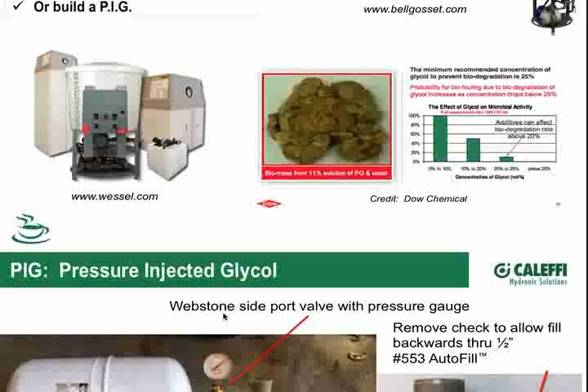This is a little system that another colleague gave me the idea for, and this is one I made. If you've got to boost up a system or fill a solar system that holds a little bit of fluid, you can pump glycol into a tank like this, put a pressure reducing valve on it, and just take it out to the job so you don't have to carry a big pump on a cart. Our fill valves can be used for that too. Our new 3/4 inch one actually has a gauge and no check valve, so you just put it on, pump it in, and blow it back out into the system.